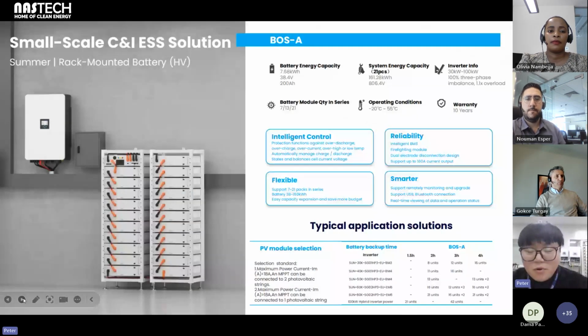The main point of our product in this meeting is the BOS-A battery, together with our 80 kilowatt inverter. Basically, this combination is like the 50K with the BOS-G battery, but upgraded to a bigger size, and the inverter casing was changed and the power rating is higher. For the BOS-A battery, we can have a maximum of 21 units in series connection, so the system voltage can come up to more than 900 volts. The inverter can also handle this voltage because the hardware inside is upgraded.